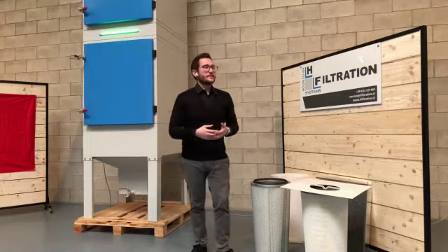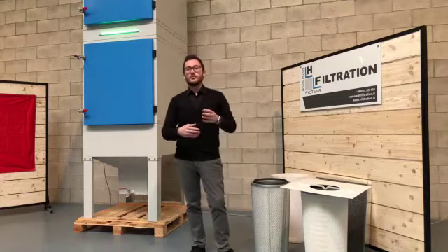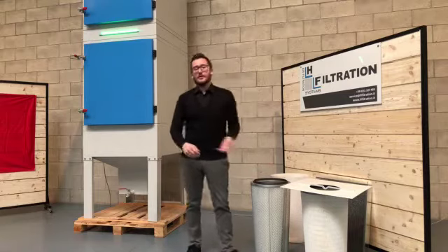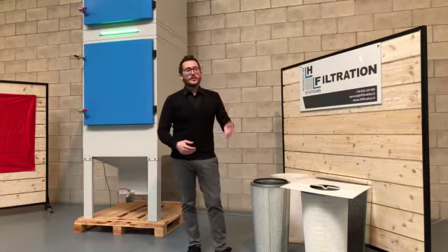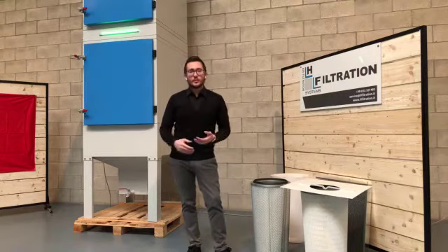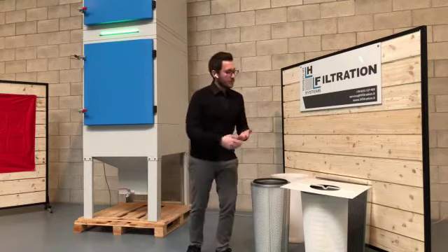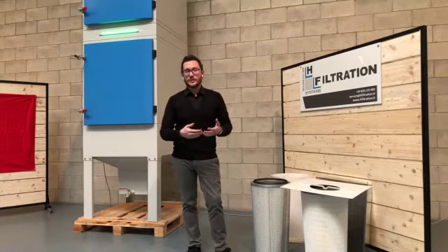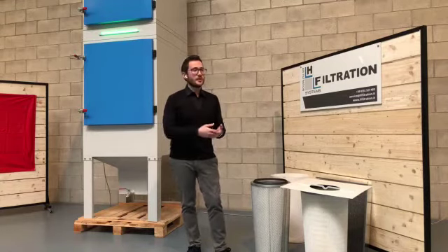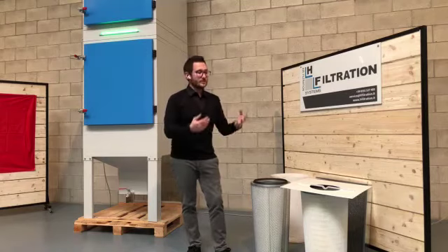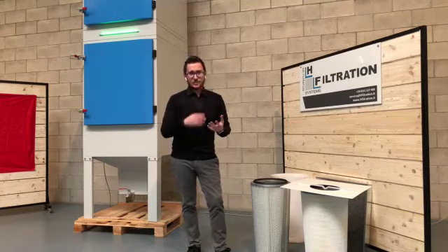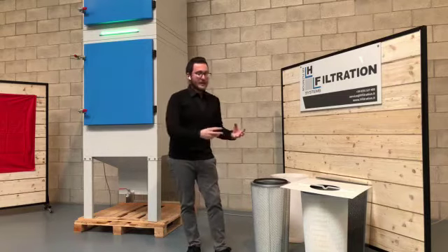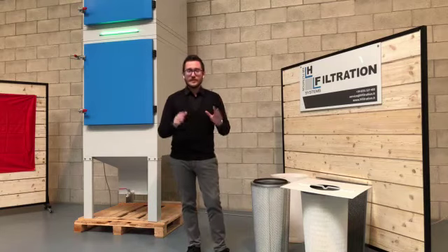So, for instance, we can speak of low duty application where the cartridges can last also more than 1 year. We can go for also 1.5 years. So we have quite a long life of the cartridge, but obviously here we are talking about a standard application where you have an 8-hour cycle, where it's not that heavy an application. But when you start having heavy duty application and so on, you can have those times reduced.